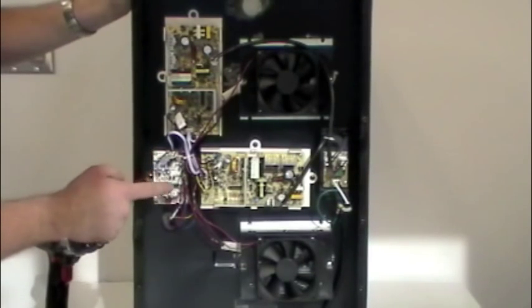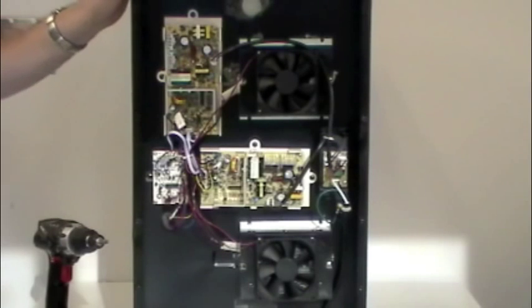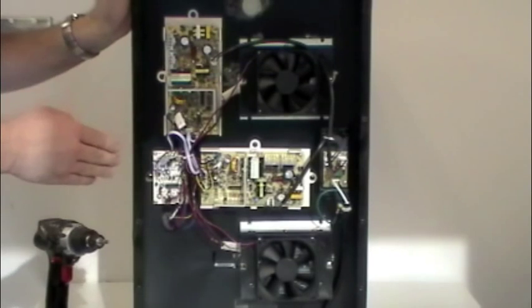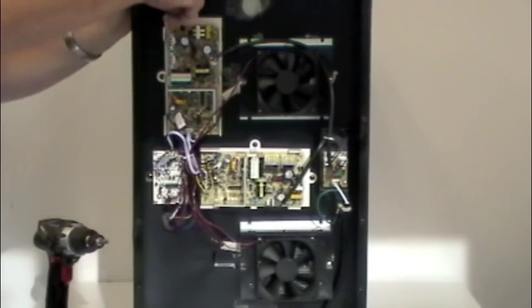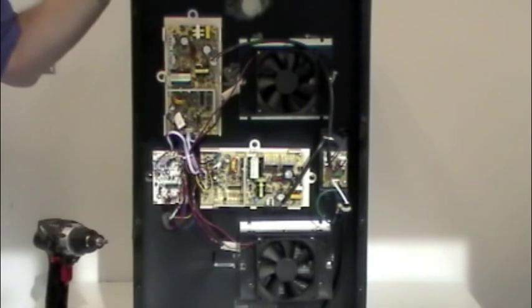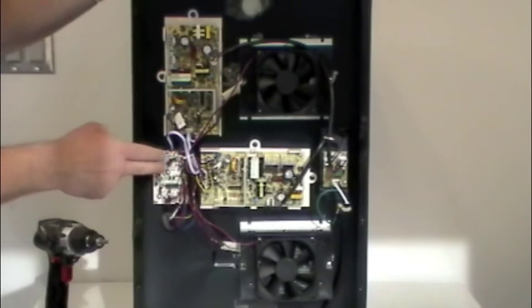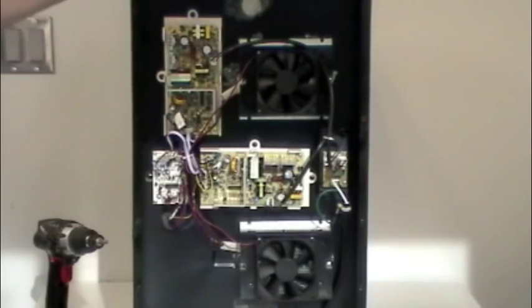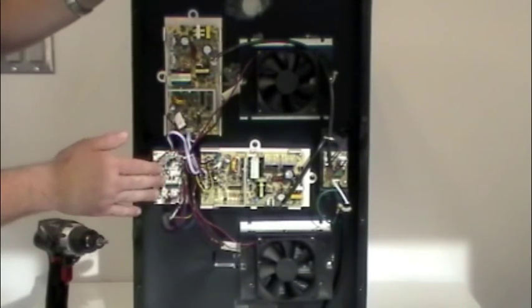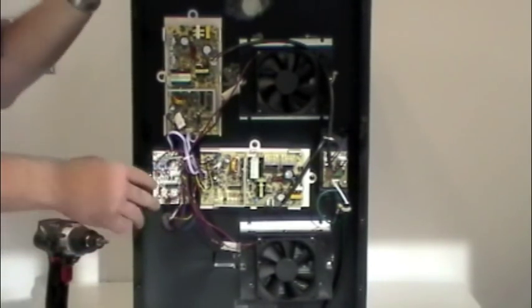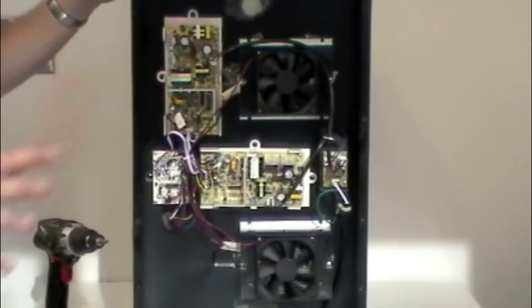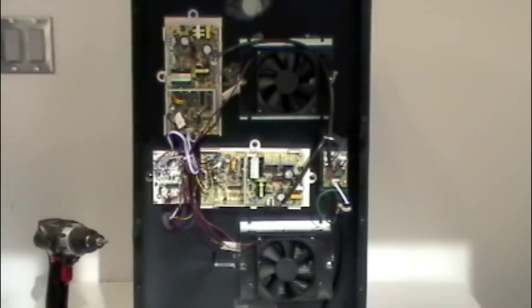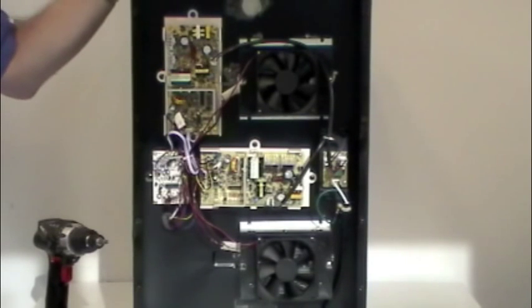The other board over here is our defrost board. If you'll remember from our first segment, we were talking about operation of the defrost board and exactly what it does. So, I'm going to go over that again. The defrost board basically goes in here and it monitors through a PTC sensor the temperature of that cold point on the other side, which is inside the wine cooler. And it keeps that temperature from dropping so low that the water condenses out of the air and then it freezes on the cold point. And it will actually cut the voltage to those nodes so that it's able to warm up in there a little bit, just temporarily enough to melt the ice.